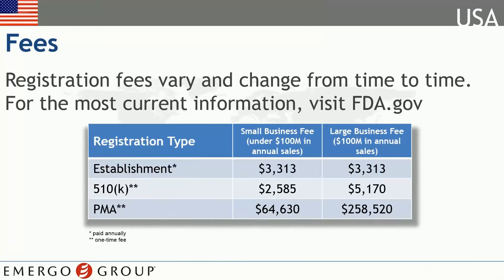Registration and annual renewal fees vary and prices change from time to time. For a complete pricing schedule, visit FDA's website. Once the FDA has cleared your device for marketing in the U.S., the agency will issue you a 510(k) clearance letter and post your 510(k) summary on its website. You will not, however, receive a registration certificate.